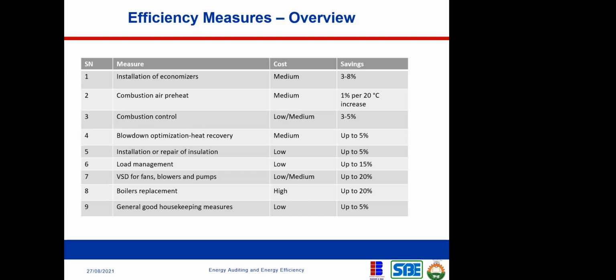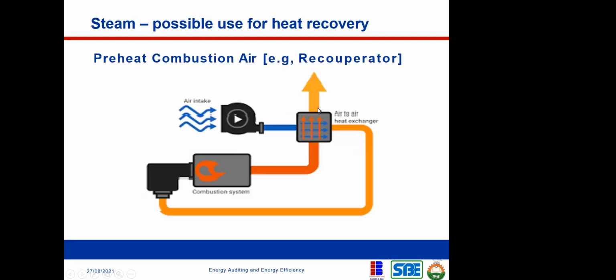Okay. So what happens is that now this is your stack, this is your exhaust pipe, right? So unlike the economizer I talked about, in this case you use air instead of using water. If you use water, it's an economizer. But if you use air, it is called a recuperator. Okay. So you pass air across the exhaust pipe to absorb the heat that would have been lost to the environment. Okay. So when that air blows through that exhaust pipe, it becomes hot.